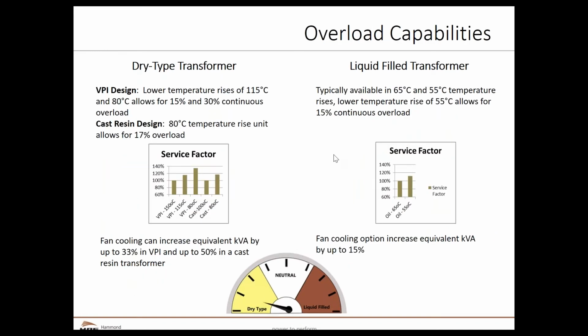When we talk about overload capabilities, dry type does have an advantage. We can do lower temperature rise transformers than what you would typically see with oil, or that oil would allow. And by having these lower temperature rise transformers, we can do two things. We can put them into hotter environments without derating. They can also give us additional capacity, provided we maintain the standard environmental temperatures.